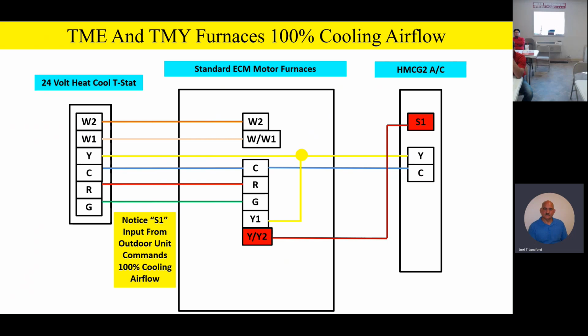So here's another way to look at it. The indoor unit is giving you two airflow speeds, 60% airflow and 100% airflow. The outdoor unit is modulating between 35 and 100% capacity based on all those parameters I just talked about, looking at sensor temperatures and liquid line temperatures and all that stuff. So the outdoor unit's just sitting there by itself, figuring out what capacity it needs to be based on all the temperature inputs it sees. The indoor unit is real simple, either 60% airflow or 100% airflow, based on that S1 signal coming in from the outdoor unit to call for second stage airflow.